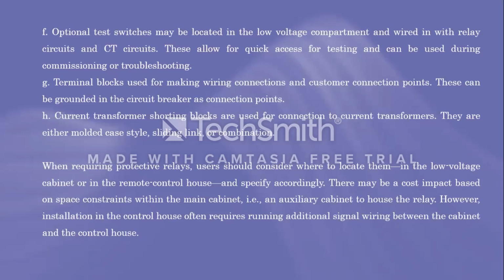Optional test switches may be located in the low voltage compartment and wired in with relay circuits and CT circuits. This allows for quick access for testing and can be used during commissioning or troubleshooting. Terminal blocks are used for making wiring connections and customer connection points. These can be grounded in the circuit breaker as connection points. Current transformer shorting blocks are used for connection to current transformers. They are either molded case style, sliding link, or combination.